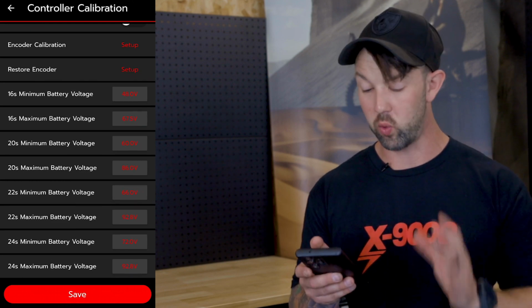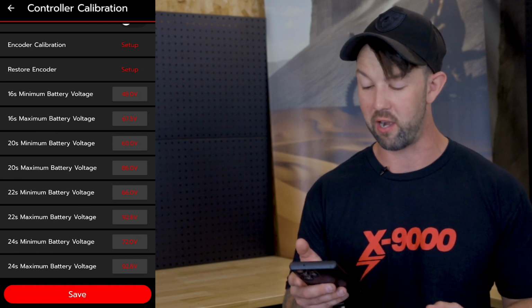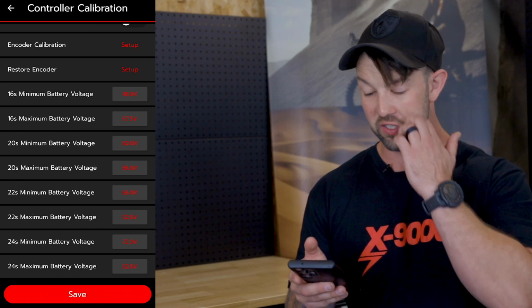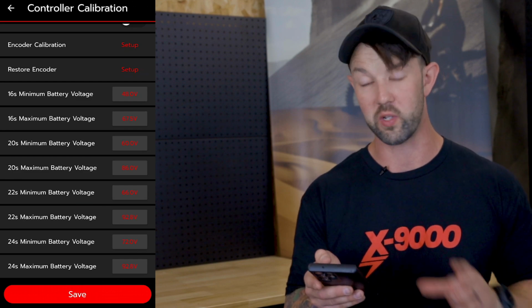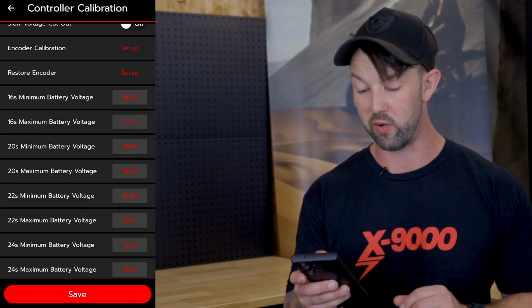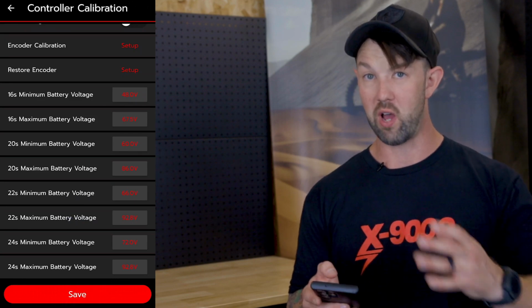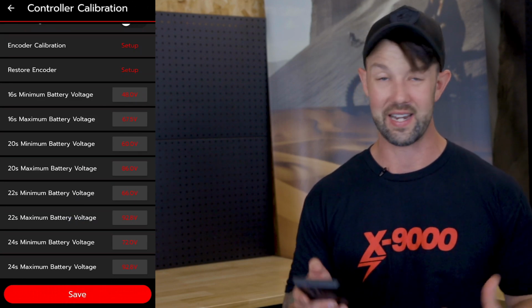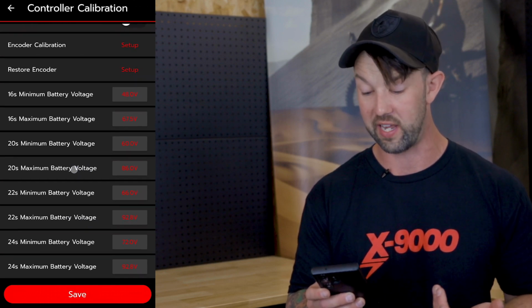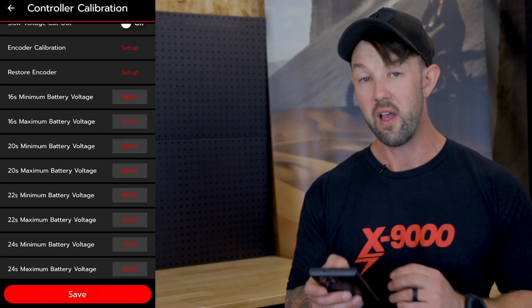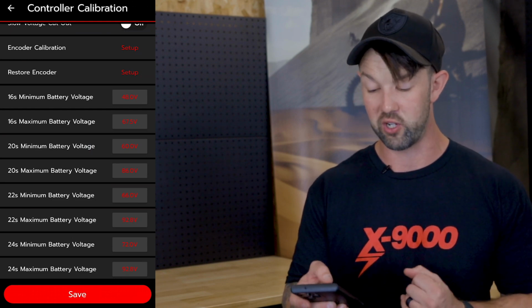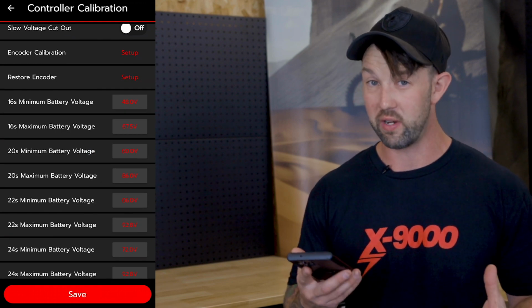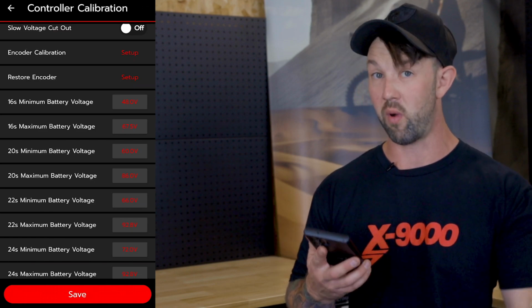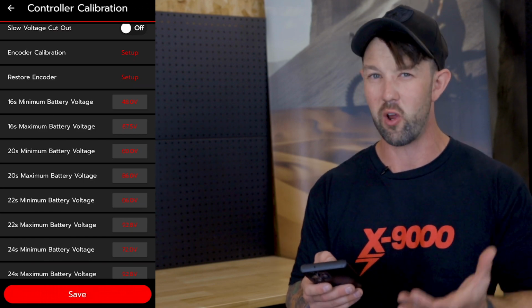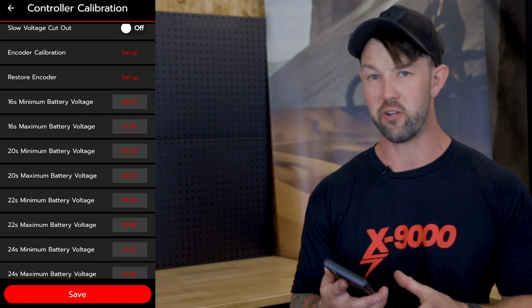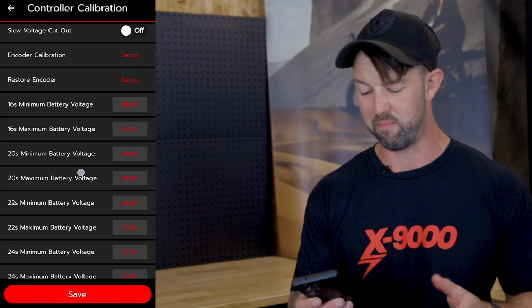We talked earlier about running a 21S battery when we didn't have a 21S option. A way to get around that is to select a 22S battery in the general settings, then come over here and physically change the voltage min and max, which allows you to run a 21S battery. Same if you had an 18S battery, you'd select a 20S setup and then physically change the min and max here. They're labeled as 20S, but at least give you that option. It may even be that your battery has a different chemistry, so the min and max voltages are different, and it still might be a 20S, but this allows you that option, so you're not stuck to one battery type or technology. It allows you to basically change it here.